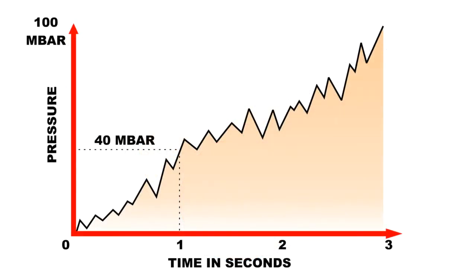Pressure can build to dangerous levels in less than a second, faster than a driver or operator can react, so the shutoff must be automatic in order to protect the silo.